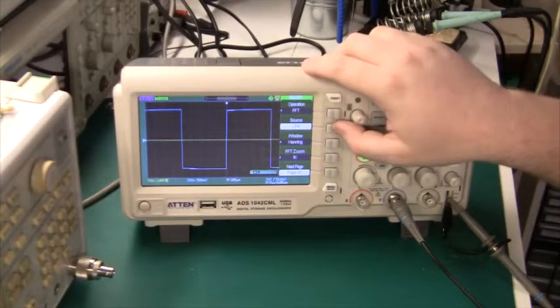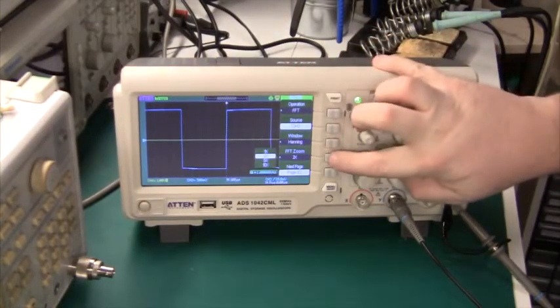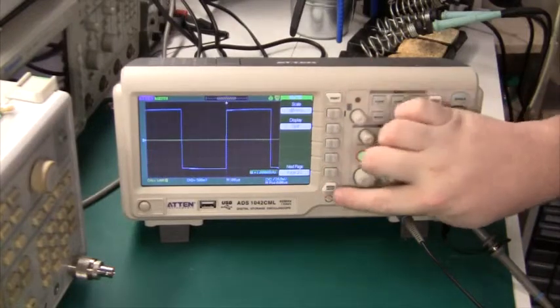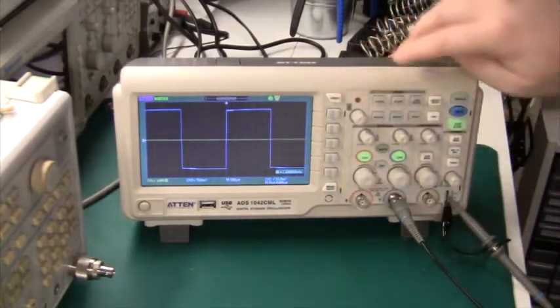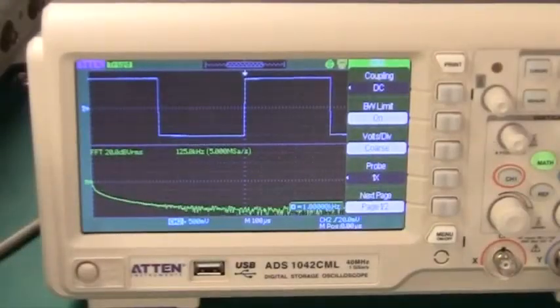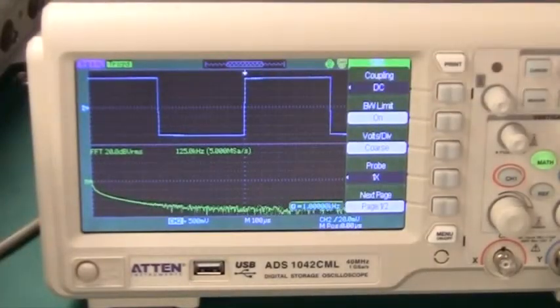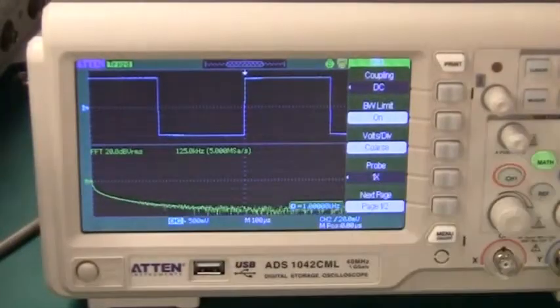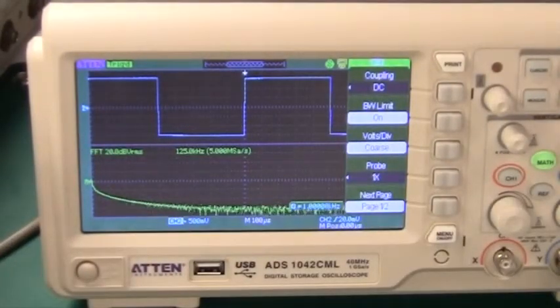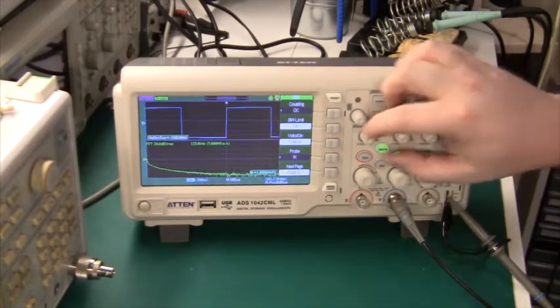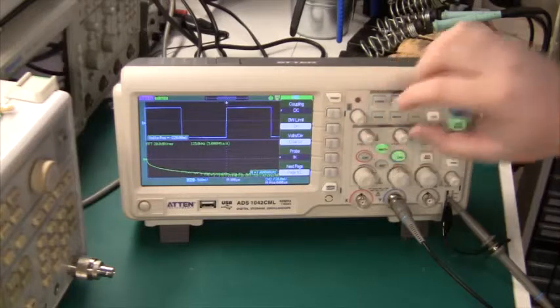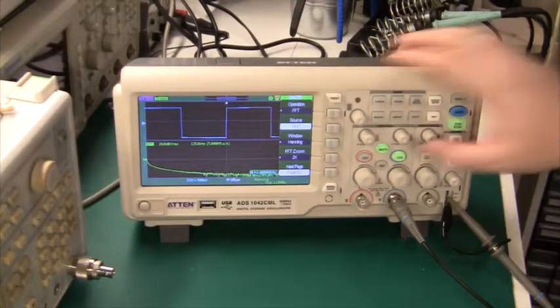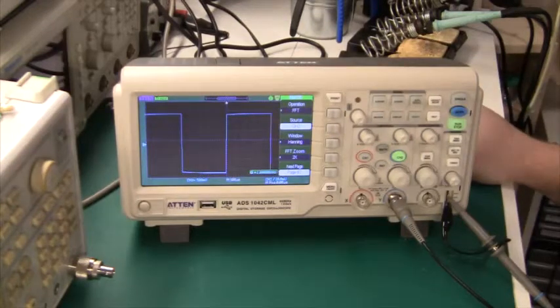And the final math function that is worth mentioning is the fast Fourier transform. Fast Fourier on channel 2. Let's see if we can get it working. There we have it. We have the square wave on top, our input on channel 2. And we have the frequency spectrum below here. While in FFT mode some of the buttons are behaving differently than in normal mode. Let's switch off the math function again and we are back to normal.